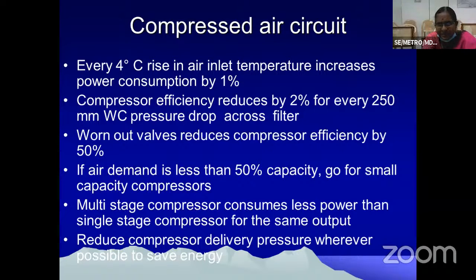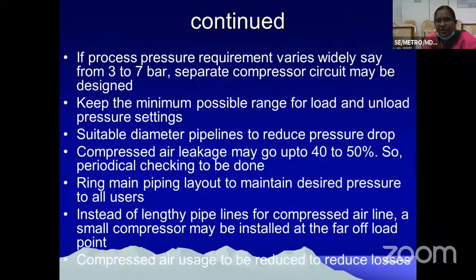Reduce compressor delivery pressure wherever possible to save energy. If process pressure requirement varies widely, say from 3 to 7 bar, a separate compressor circuit may be designed. Keep the minimum possible range for load and unload pressure settings. Suitable diameter pipelines to reduce pressure drops. Compressed air leakage may go up to 40 to 50%. Have periodical checking done. Ring main piping layout to maintain desired pressures to all users. Instead of lengthy pipelines for compressed air lines, small compressors may be installed at the far-off load points. Compressed air usage to be reduced to reduce the losses.